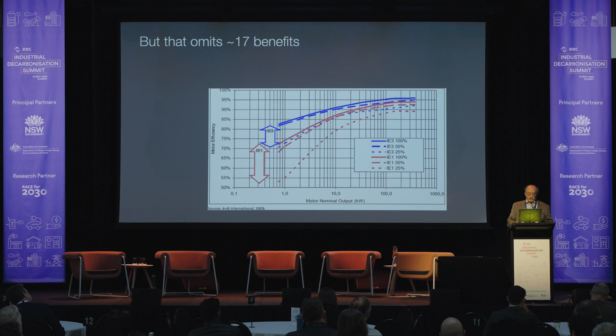So you also then find the flatter efficiency curve across the load range improves flexibility. Premium motors typically have higher and flatter power factor that reduces distribution losses and capacity needs. They run cooler, so they have lower resistive loss. They have longer life because each 10 Kelvin of reduced temperature roughly doubles expected life. They have longer grease life, so you need to lubricate them less often and with less downtime.